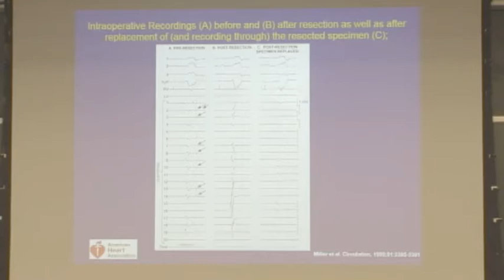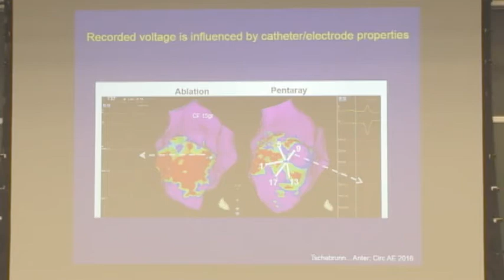Another problem with just using voltage is that the local amplitude of electrograms is influenced by a number of factors, not just the electrode itself. If you take a standard ablation catheter and look at the area of low voltage that's reported, you see a fairly extensive low voltage area in this person. But when you use the PentaRay, a catheter with much smaller electrodes, more closely spaced, you see a much smaller and much more heterogeneous area of very low voltage. So local electrode size will affect the characteristics of the voltage that you record.